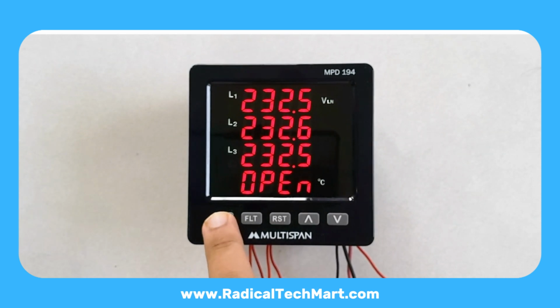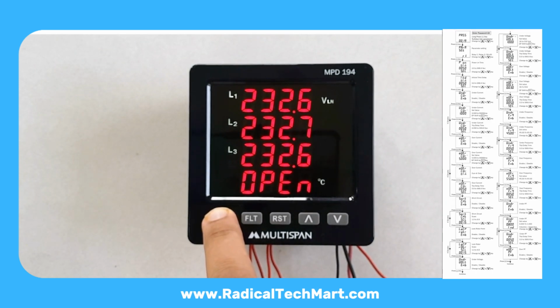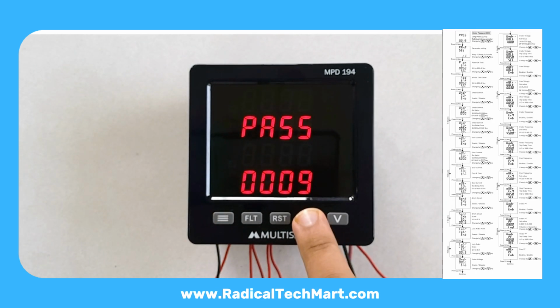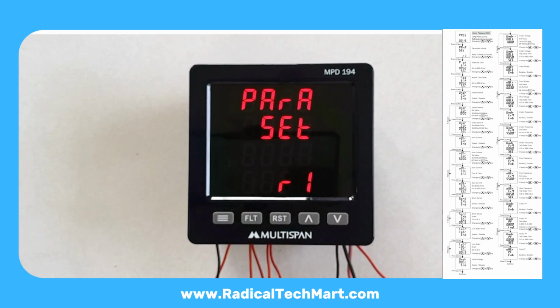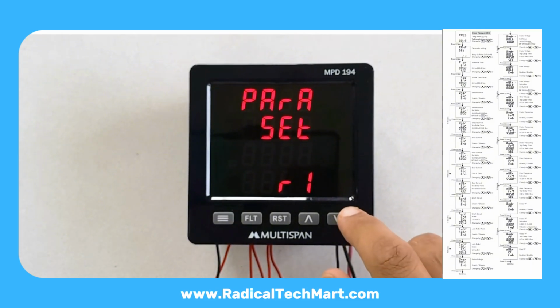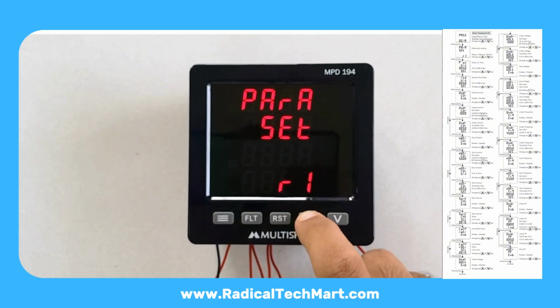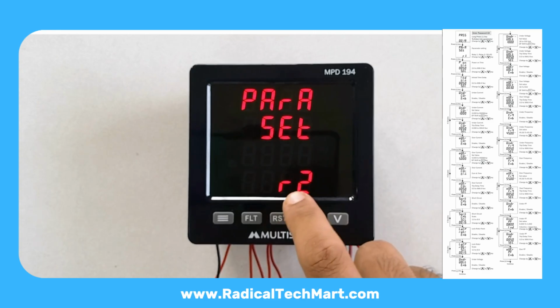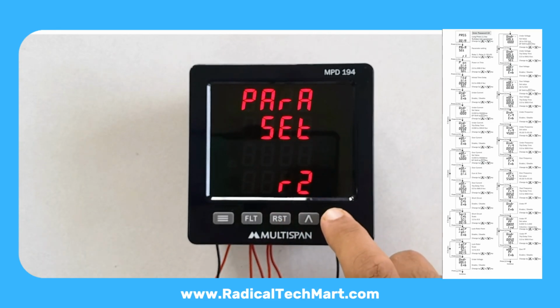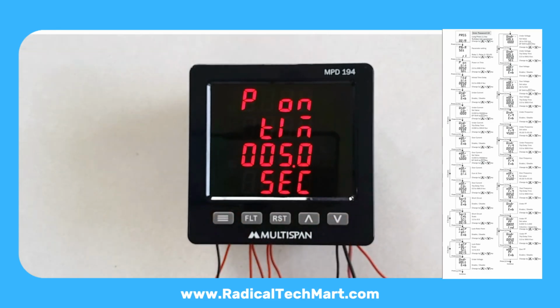Now we go to the protection menu. Press set, then press and hold set again. Enter password 19. Press set. The first option is for relay 1, R1. If you press the up arrow, you can jump to relay 2, R2, settings. We'll first configure relay 1.